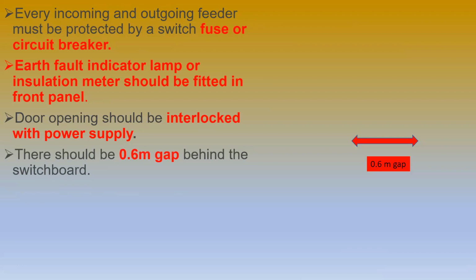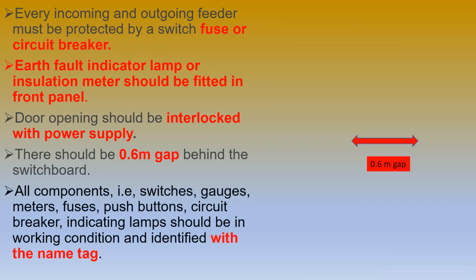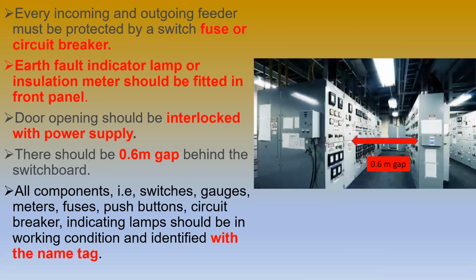And there should be a 0.6 meter gap behind the switchboard. I'll show the diagram here. So this is the switchboard. Here we have a 0.6 meter gap between the switchboards. So if any arcing or arc blasting happens, it should not affect the other boards, and should not develop fire or explosion further. So there should always be a gap and proper ventilation.